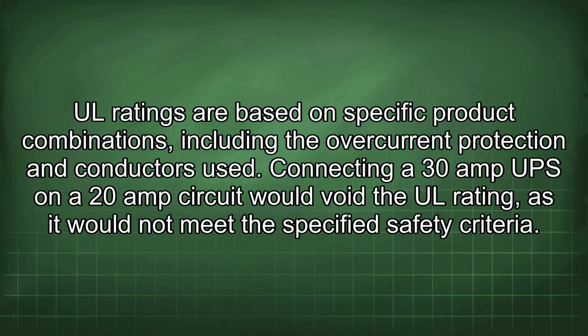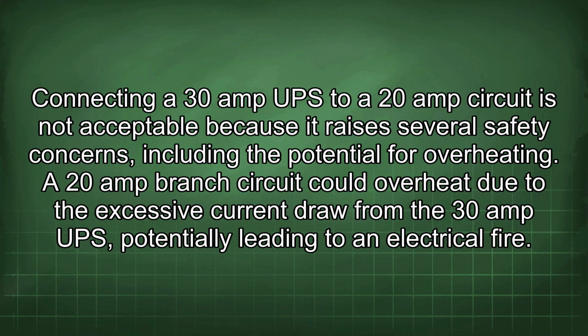UL ratings are based on specific product combinations, including the overcurrent protection and conductors used. Connecting a 30 amp UPS on a 20 amp circuit would void the UL rating, as it would not meet the specified safety criteria. Connecting a 30 amp UPS to a 20 amp circuit is not acceptable because it raises several safety concerns, including the potential for overheating.